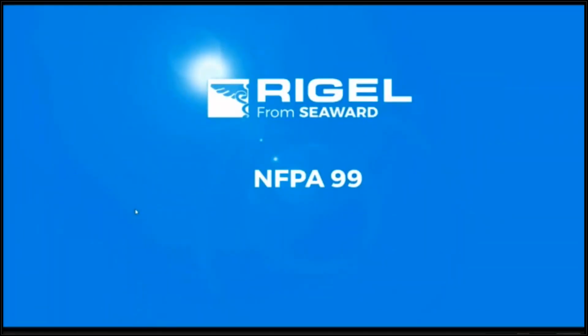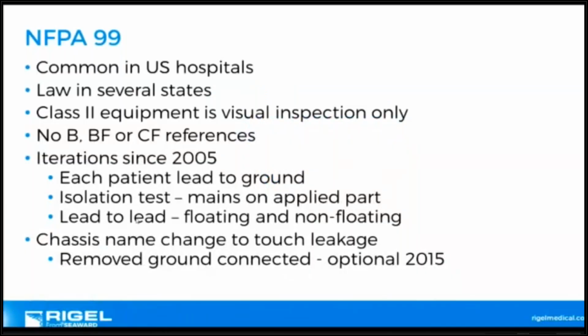Right, NFPA 99, common in US hospitals, law in some states. How it differs from previous testing, class 2 equipment, visual inspection only. So you don't test the electrical properties of a class 2 device when testing NFPA 99. There's no real references to B, BF, CF. And there's been various iterations since 2005.